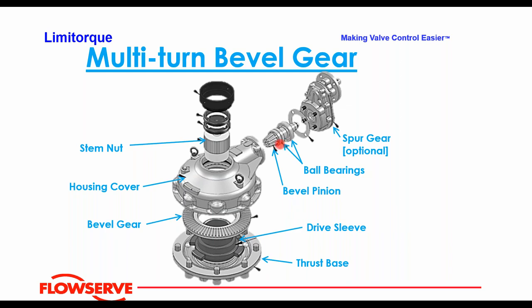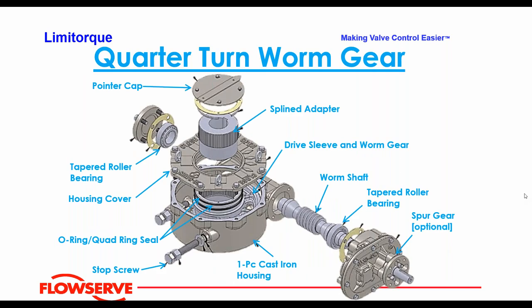In the multi-turn bevel gearbox you have the bevel pinion and the bevel gear which drives the drive sleeve — typically used for automating multi-turn sluice and slide gates. The quarter-turn worm gear is mainly for ball, plug, and butterfly valves; this one is shown with the optional spur gear. It has travel stops for end of travel, and again these gear types can be coupled with electric actuators to gain mechanical advantage.